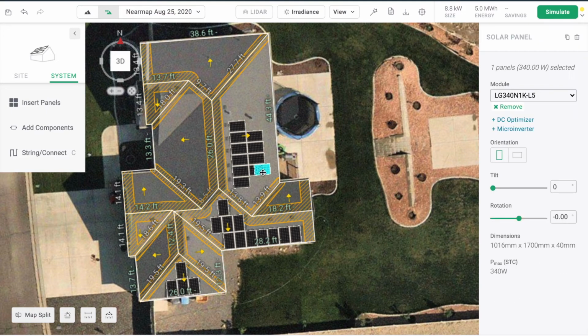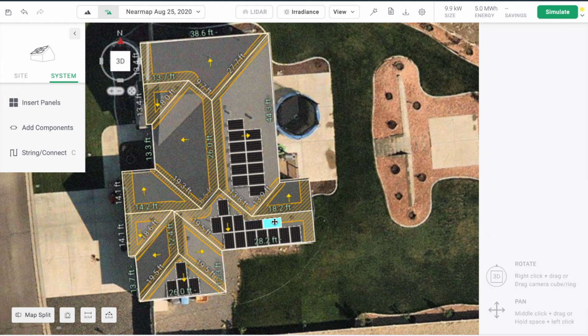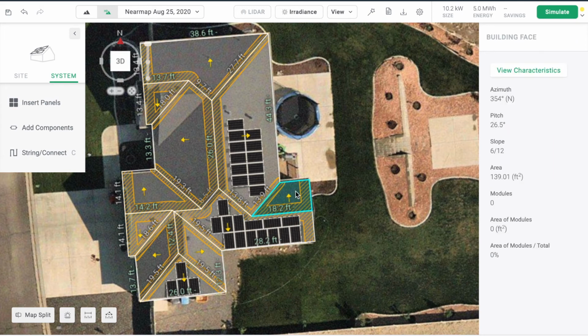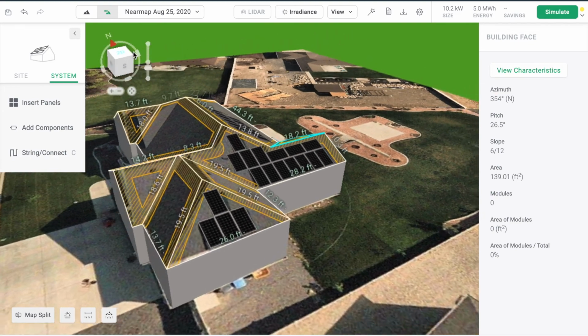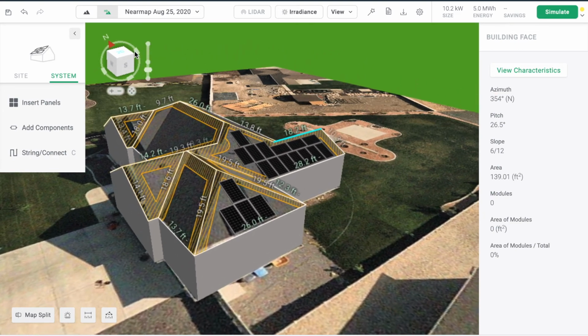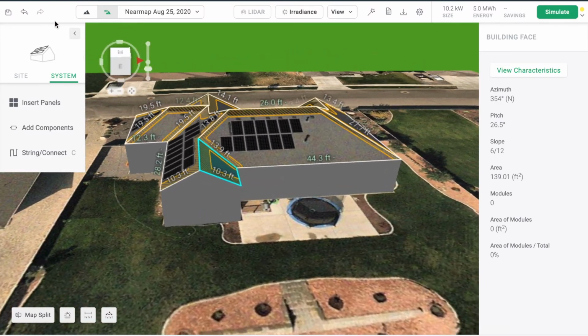We didn't have to update any wiring in the attic, didn't have to upgrade the inverter. It was relatively easy just to tie into those circuits and add those panels. Now, if you wanted 11 panels, that may have been pulling new wire or redoing all the circuits on the roof or maybe upgrading the inverter, and that would have been very costly to do that. So in this situation, it made a lot of sense. Even though the customer only needs about 7 solar panels, it made sense to add 10. It fit on the roof perfect and it maxed out the inverter.